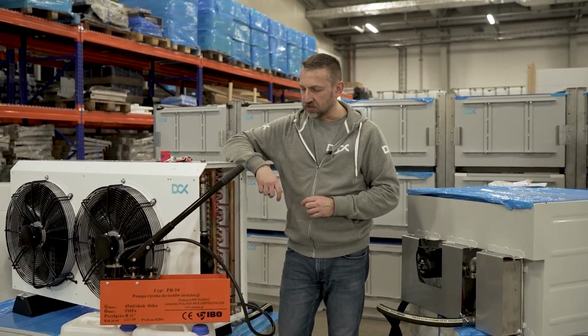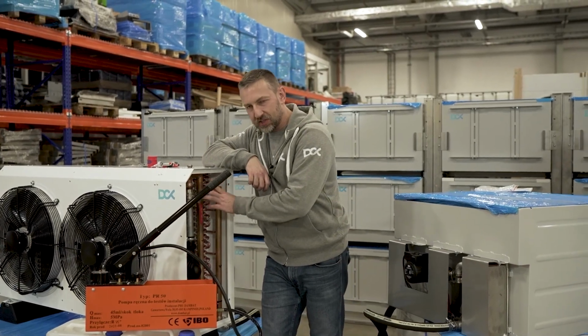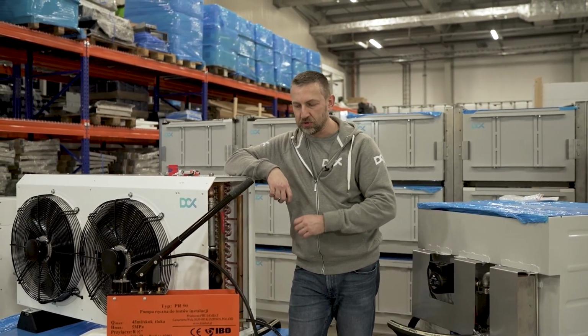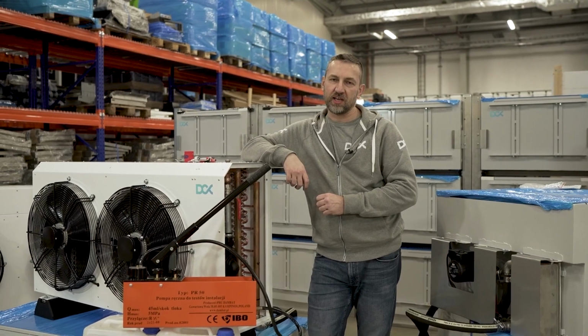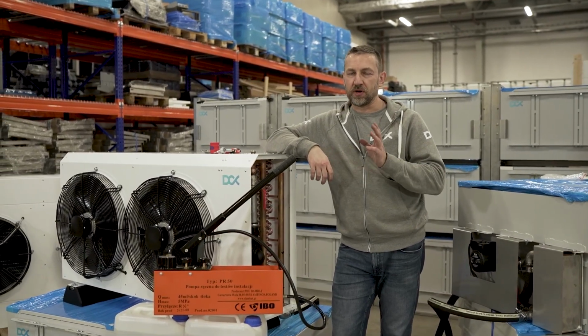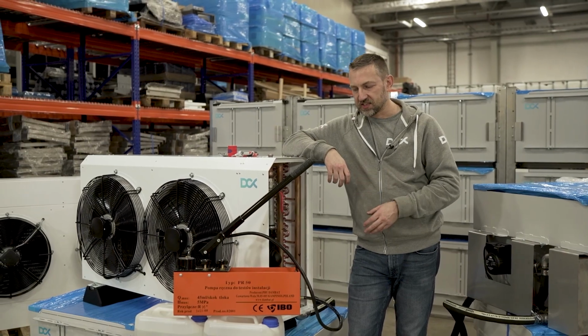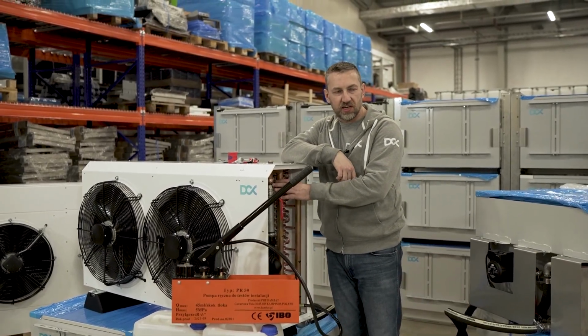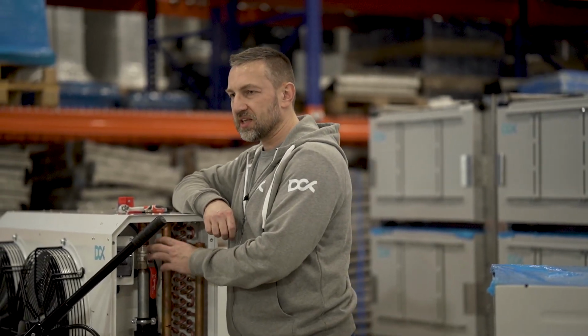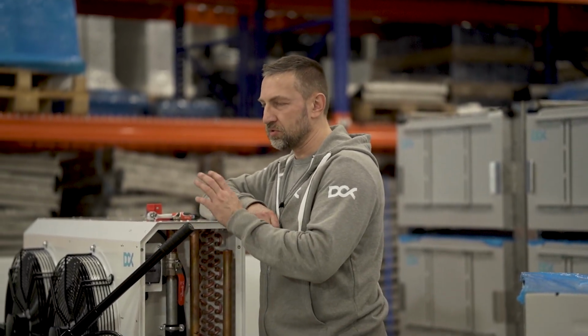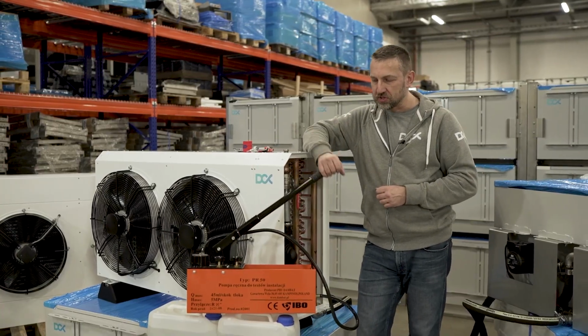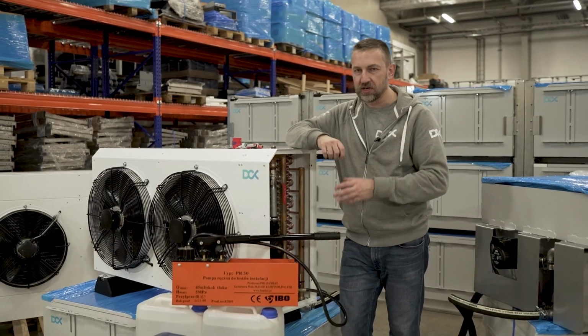But having said that, you need to remember, if you're using demineralized water inside of the system, you are pressurizing it. If there will be negative temperature, -5, -10 degrees Celsius or less, the water will freeze inside if you stop your system. So if you stop your system because of a power failure, or you perform any maintenance, then the water will immediately freeze in those small coils and you will ruin your dry cooler. You don't want that. So in that case, we'll be using the proper glycol amount.